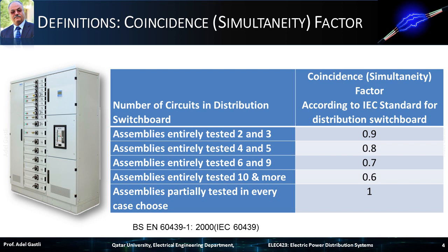The fully tested assemblies are more trusted in their ratings, and therefore coincidence factor values below 1 can be considered, while those partially tested may not be fully trusted in their ratings, and therefore it is recommended to take a unity coincidence factor, which means also unity diversity factor, and hence diversity in the load shall not be considered. According to this table, for assemblies entirely tested with 2 and 3 circuits, the standard coincidence factor is 0.9; for 4 and 5 circuits, 0.8; for 6 to 9 circuits, 0.7; and for more than 10, it is 0.6. For assemblies partially tested, in every case we choose the coincidence factor as unity. Notice that the larger the number of circuits, the lower is the coincidence factor.